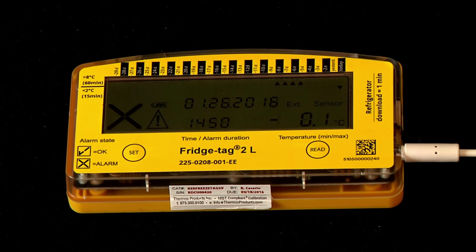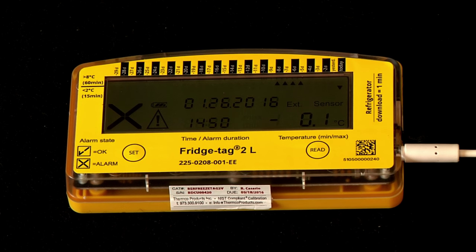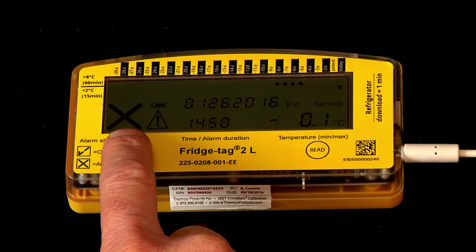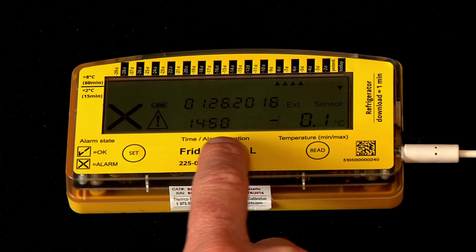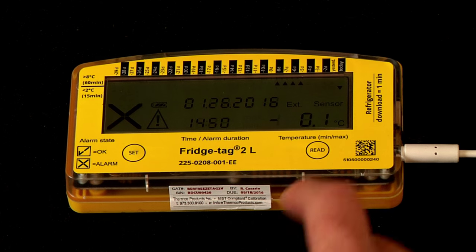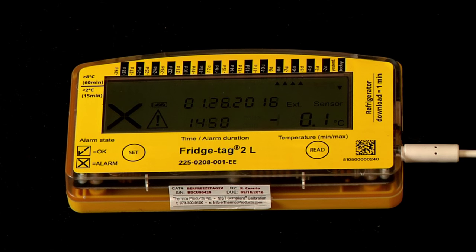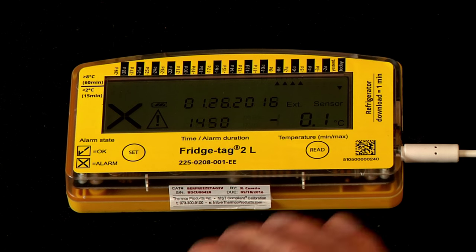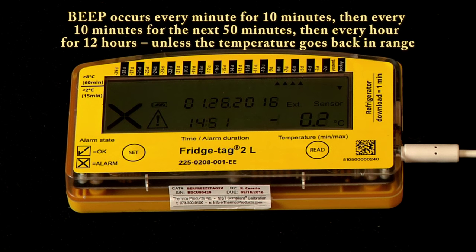That sound is the Fridge-tag 2 L model's audible alert signal, telling you there's an alarm in your storage unit. It also demonstrates visually on screen with an X that there's an alarm, showing the current date, time, and that the temperature is too low — negative 0.1 degrees C. The alarm is indicated with a down arrow under today, and previously there were alarms a few days ago for being too warm. If there's an alarm, it's important to adjust the temperature in your storage unit to get it back within the acceptable range — you may need to move your vaccines.